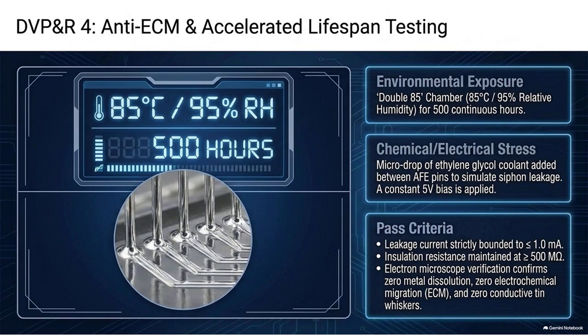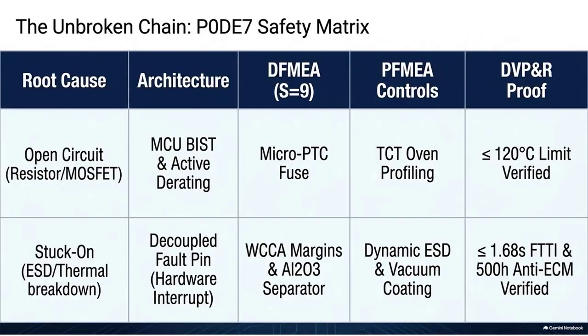They inject a massive instantaneous 4.30-volt analog signal directly into the AFE chip. A simulated catastrophic overvoltage event with zero warning. And the hardware comparator has to spot it in microseconds and pull the physical fault pin low, while the software is simultaneously racing to filter the noise, confirm the voltage for the 1.68 seconds, and log the P0DE7 code to memory. But the only metric that matters is the total response time to mechanically sever the high-voltage contactors, from the microsecond that fake voltage hits to the microsecond the relays snap open and current hits zero.